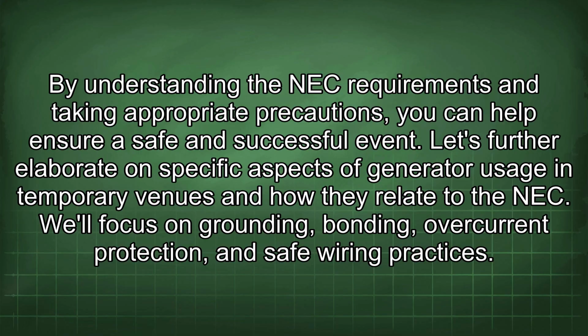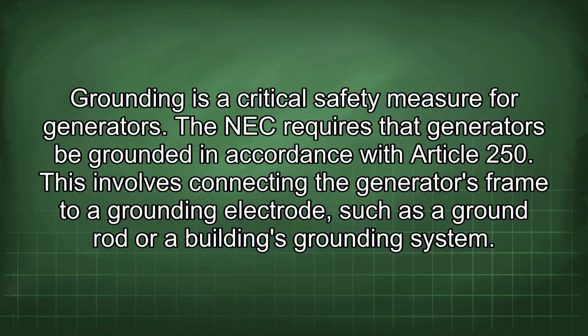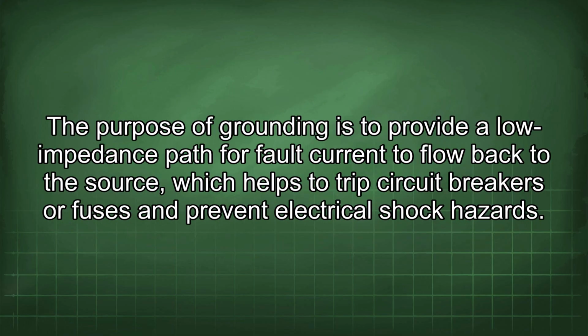Let's further elaborate on specific aspects of generator usage in temporary venues and how they relate to the NEC. We'll focus on grounding, bonding, overcurrent protection, and safe wiring practices. Grounding is a critical safety measure for generators. The NEC requires that generators be grounded in accordance with Article 250. This involves connecting the generator's frame to a grounding electrode, such as a ground rod or a building's grounding system. The purpose of grounding is to provide a low impedance path for fault current to flow back to the source, which helps to trip circuit breakers or fuses and prevent electrical shock hazards.